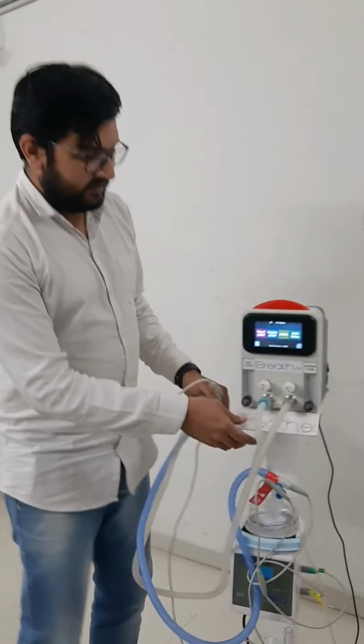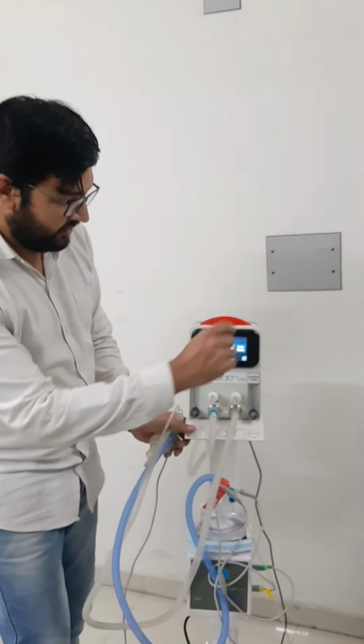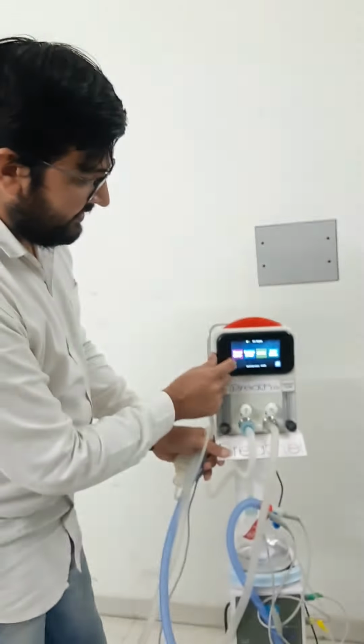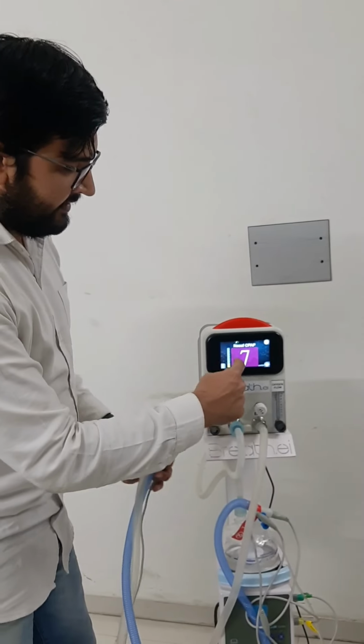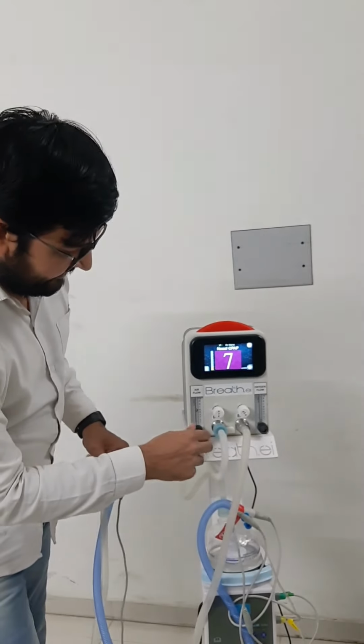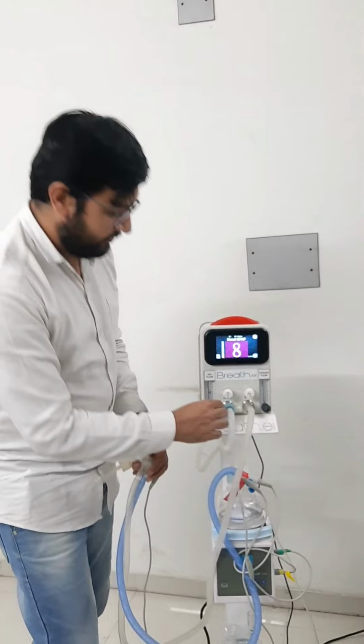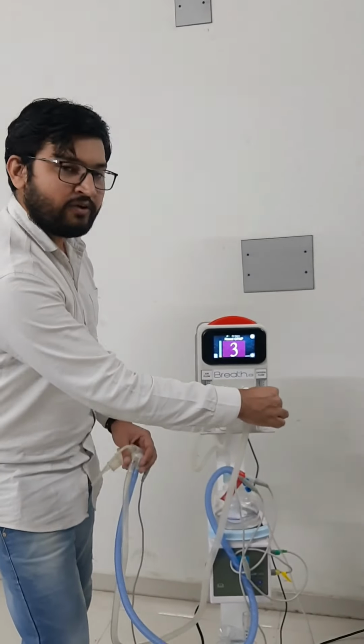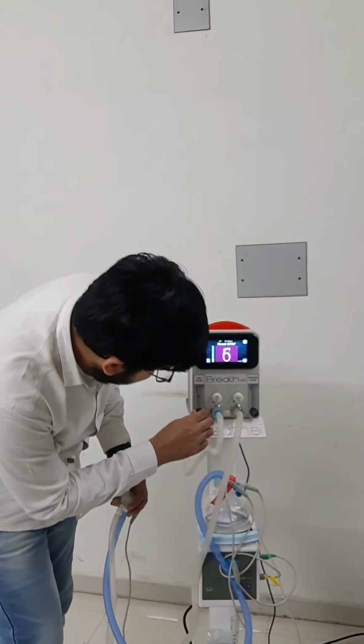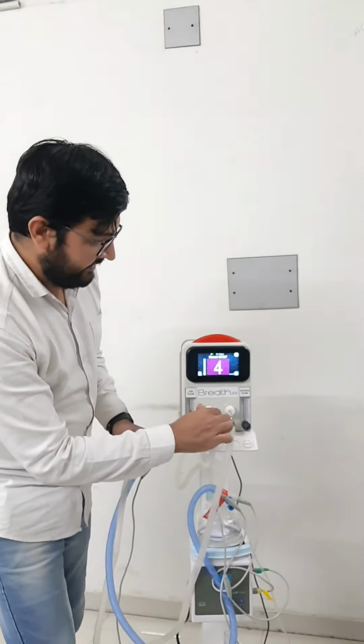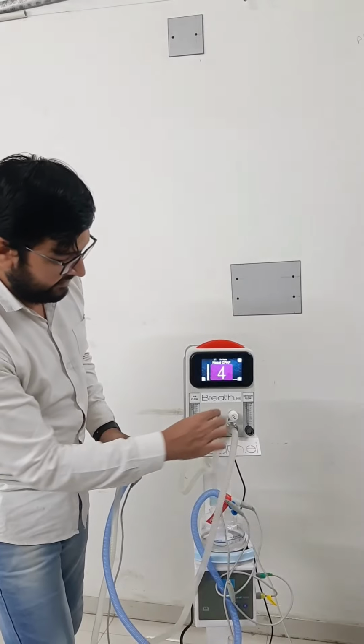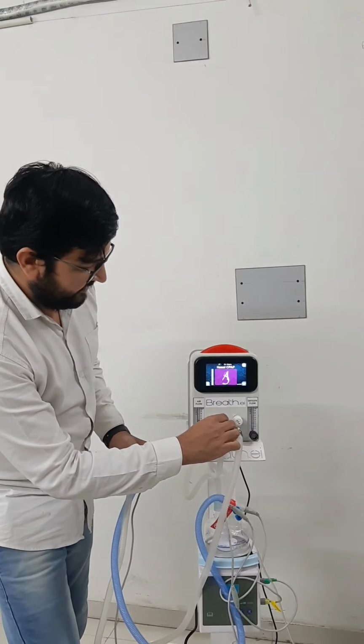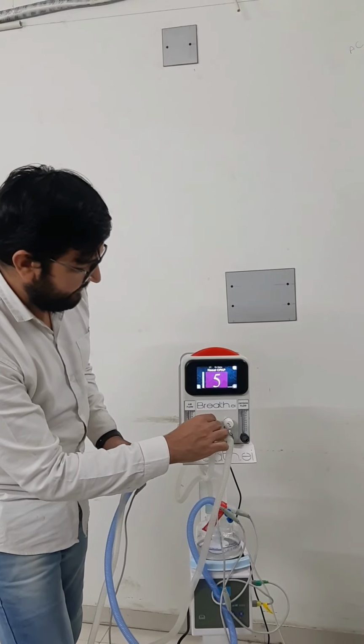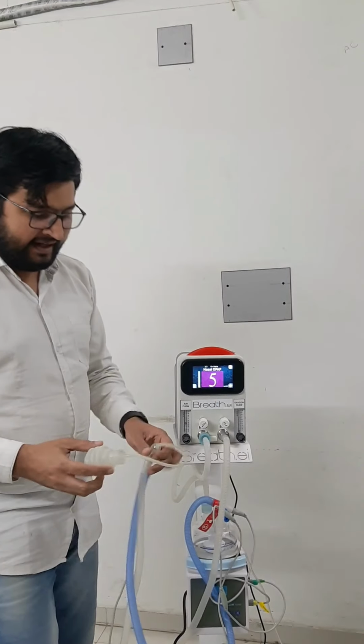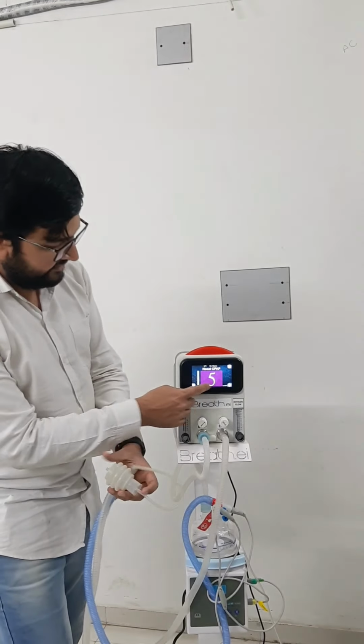First of all, we start with the nasal CPAP mode. To start nasal CPAP, just click on the nasal CPAP mode button and the mode will activate. Now set the required flow from these two flow meters, air flow meter and oxygen. As required, you have to set the flow and FiO2 accordingly, as per the FiO2 chart. Then you have to set the PEEP from this PEEP knob. Currently I have set a PEEP of 5.